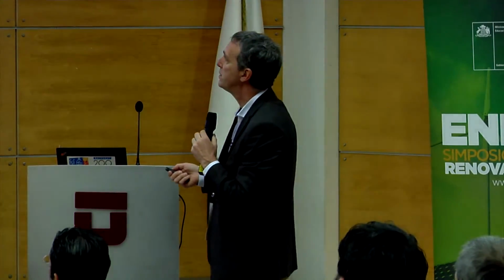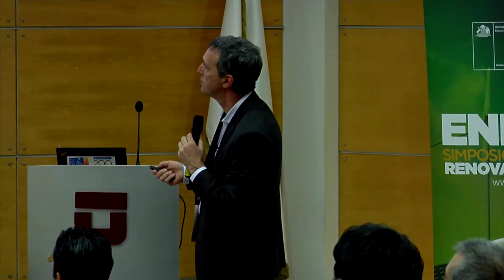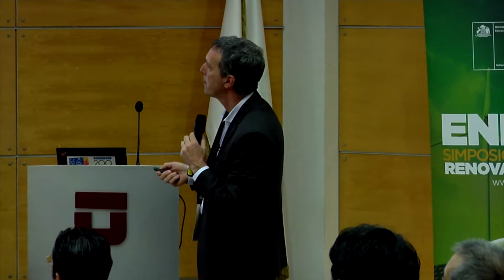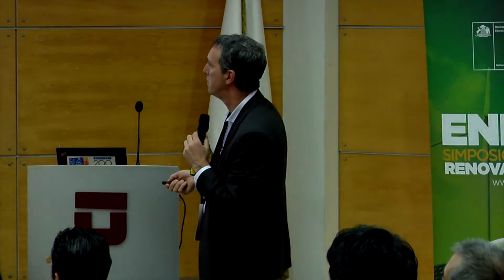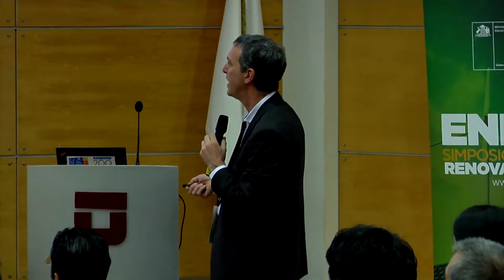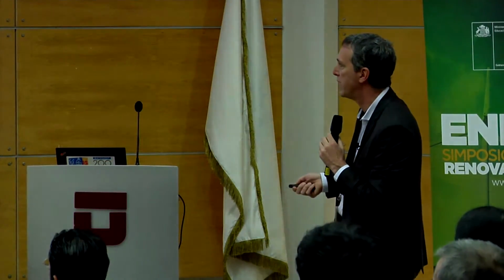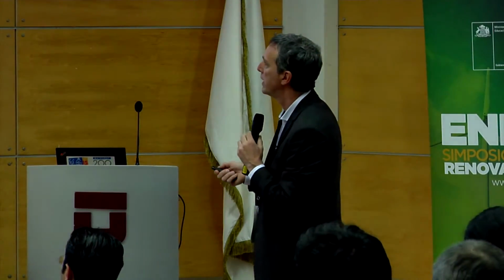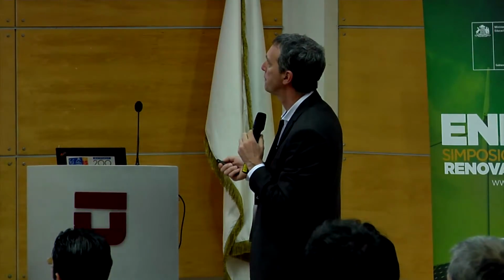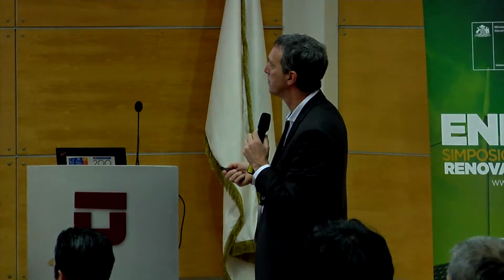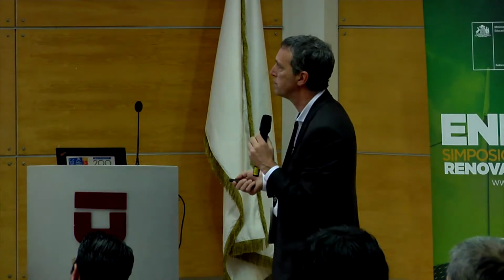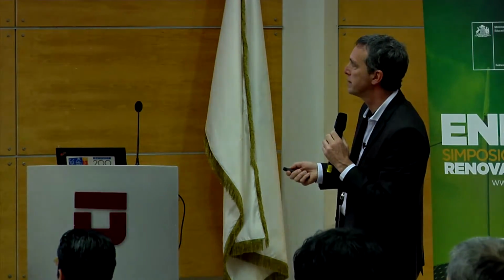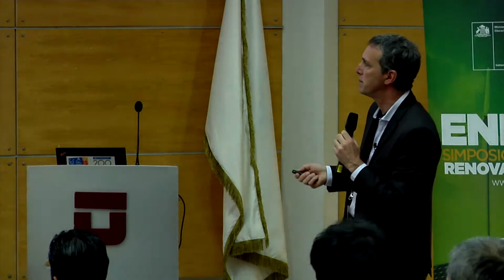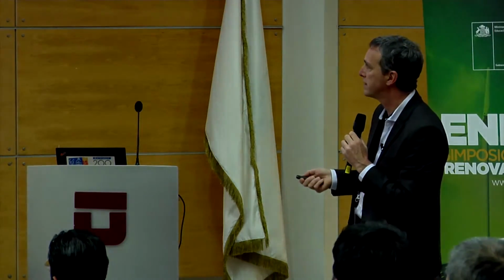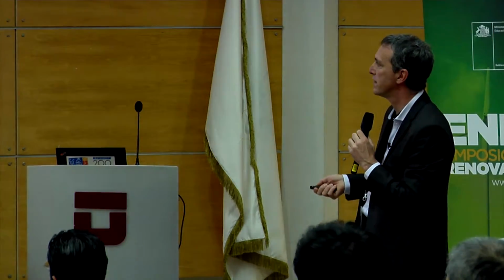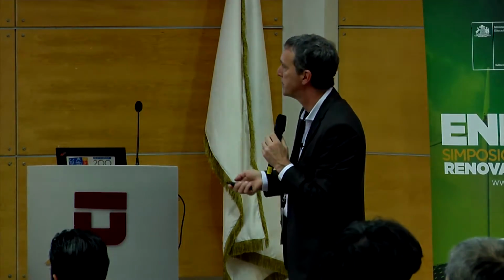And this shows the medium voltage testing. So you can see that the voltage here is 3.3 kilovolt. And then it shows switching frequency approximately 250 Hertz. And these figures are more or less for a 205 kilowatt power flow. So you can see power flow from port 1 to port 2, power flow from port 2 to port 1. And these are the port 1 waveforms, and these are the port 2 waveforms, similar to what we've seen earlier. The red is the current, blue is the voltage, and the green is the PWM voltage. So you can see how the system has been tested and validated also for high power flow in our labs.